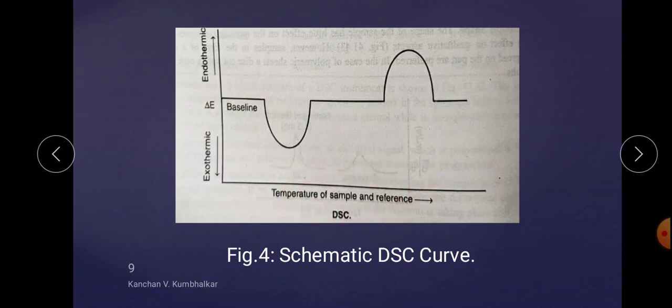It is worthy to note that the measurement of delta E is effective. Delta H has been measured in the format of delta E. It is an effective and direct measurement of energy change in the sample. This makes DSC particularly appropriate as a technique for the measurement of delta H values.